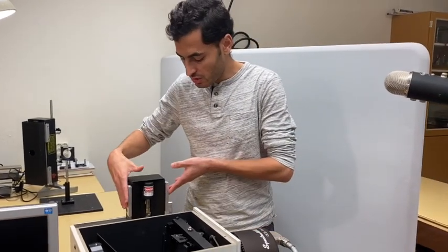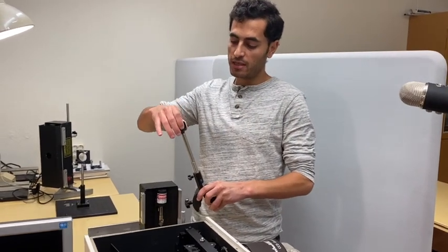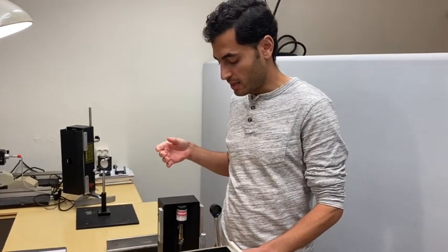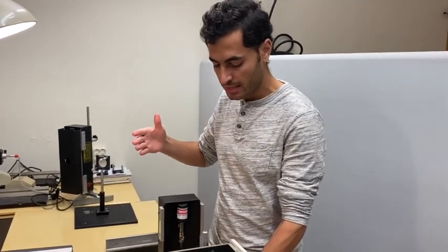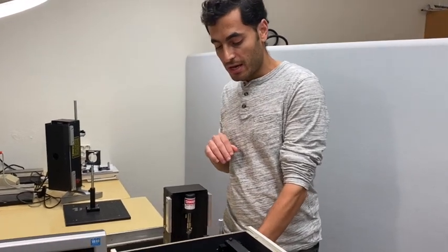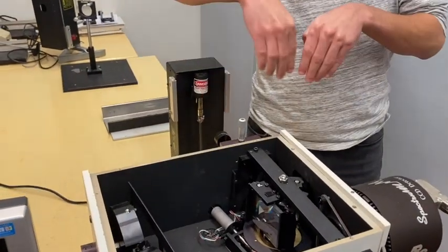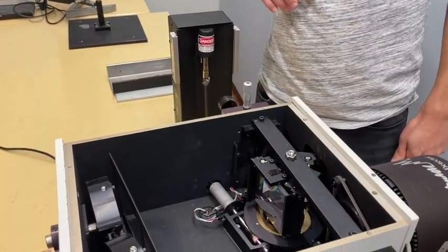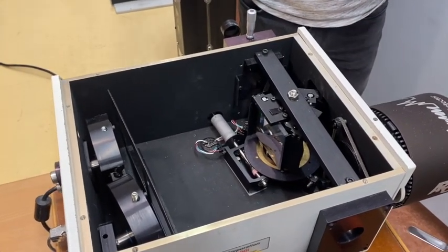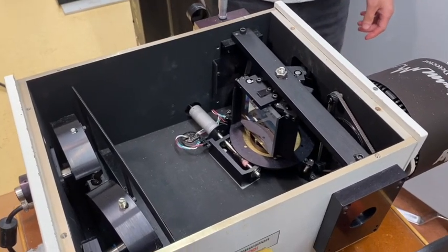So you have the light source, and then you have a filter, two of them actually, and these will be used to basically attenuate the light when needed. Depending on what line you're looking at, sometimes you want less light because it's too bright. After the filter, you have a slit whose width you can control. We're using this micrometer, and you need to align it once, and then that will set how much background you have.